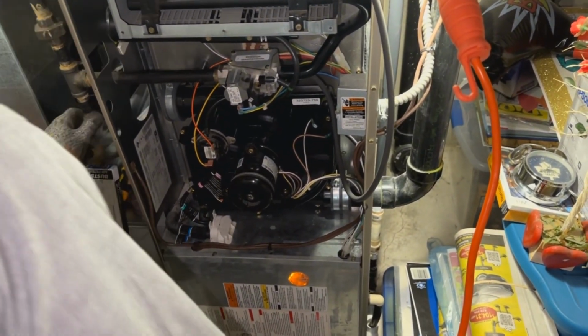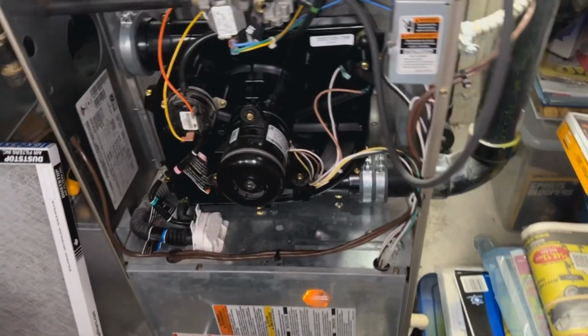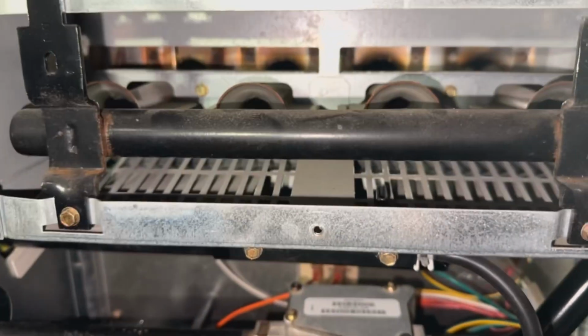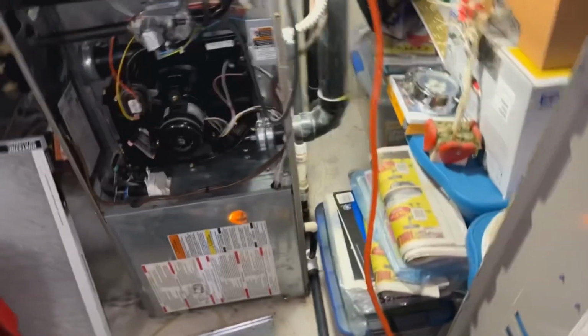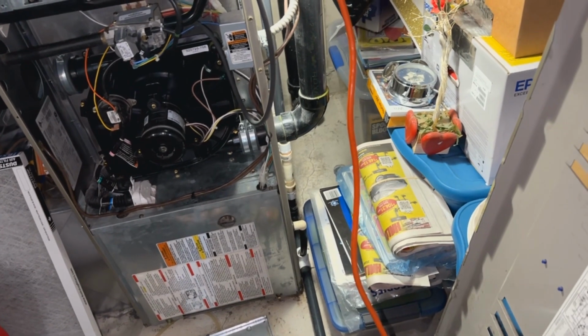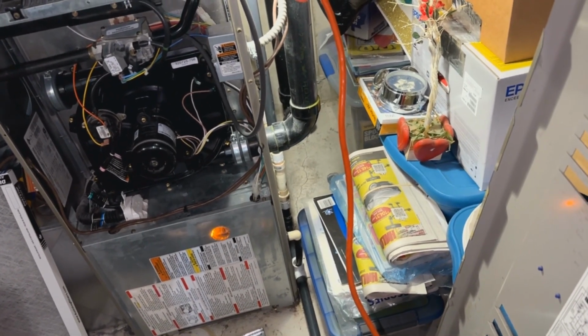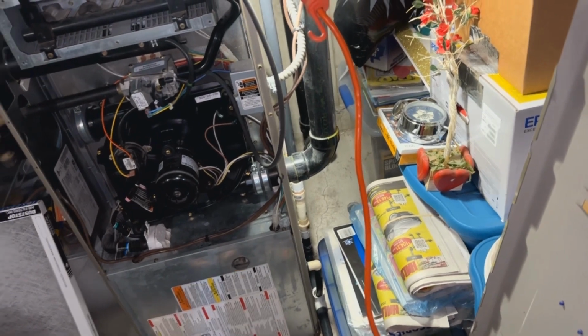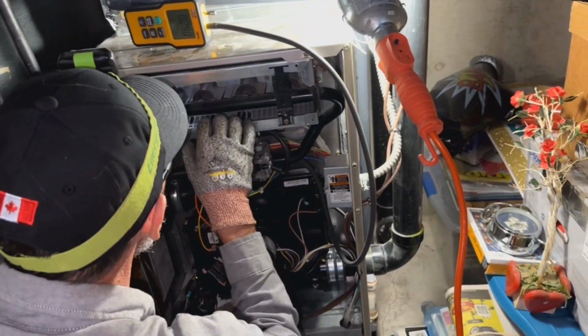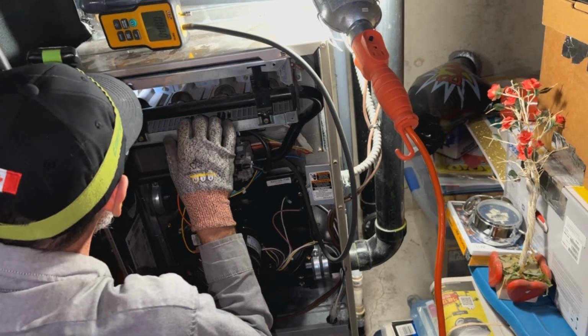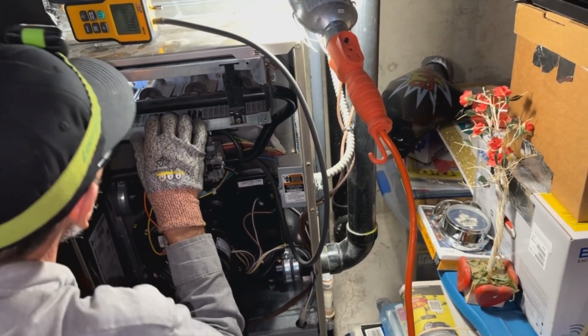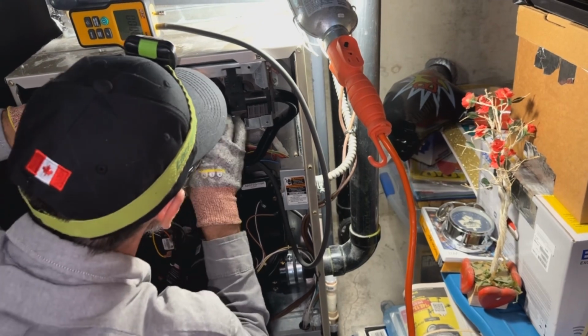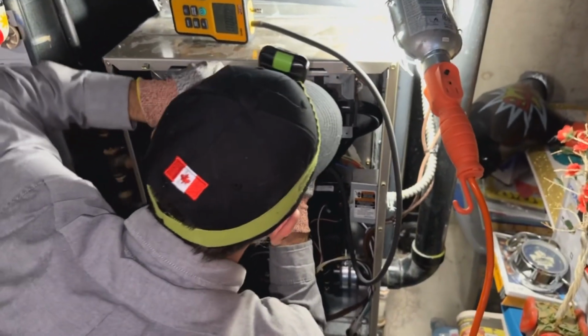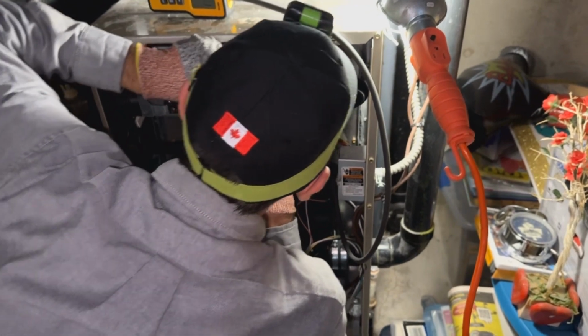So for a Carrier furnace, which is what I got, when there's a call for heat, the inducer fan comes on, and like I mentioned before, eventually that motor will start up, closing the switch and firing up the burners. Let me take a peek inside, see what your heat exchanger is looking like. We can tell it's not going to be bad though, because we had a nice CO number outside. A little bit of rusting around your burner ports, that's about it. The metal still looks good in this one, buddy. A little bit of rust stains.